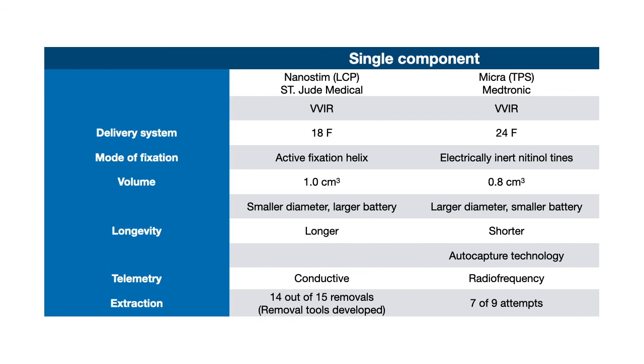The two available single-component leadless pacemakers are the Nanostim from St. Jude Medical and the Micra from Medtronic. Both systems are single-chamber rate-responsive pacemakers. The Nanostim actively fixes into the myocardium through a helix by screwing it, but the Micra system passively fixes into the myocardium through inert nitinol tines. The Nanostim system is smaller in diameter and has a larger battery that gives it a longer longevity. This is in contrast to the Micra system, which has a larger diameter and a smaller battery with a shorter longevity, but it uses auto capture technology so as to conserve energy.